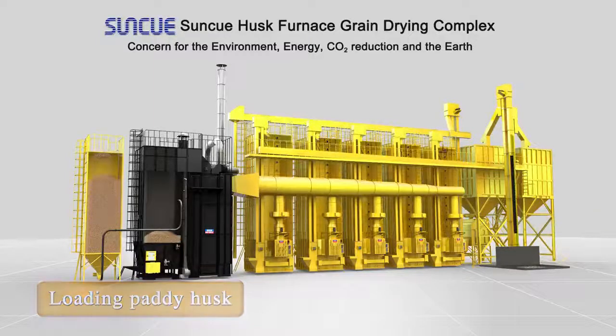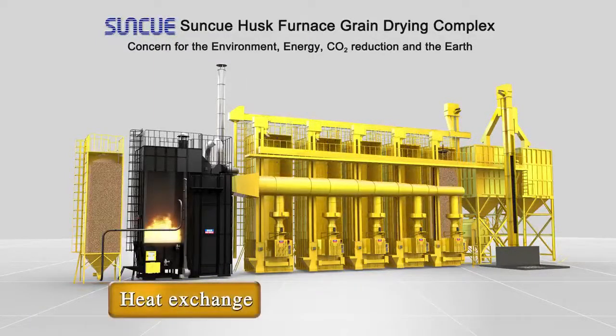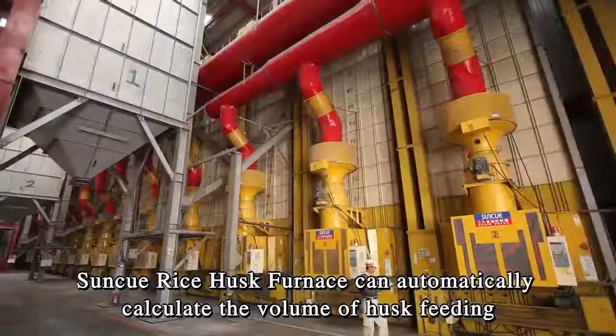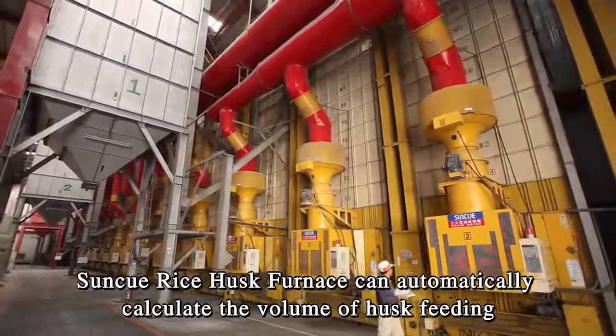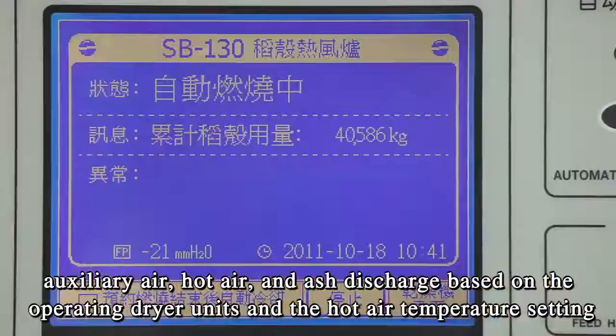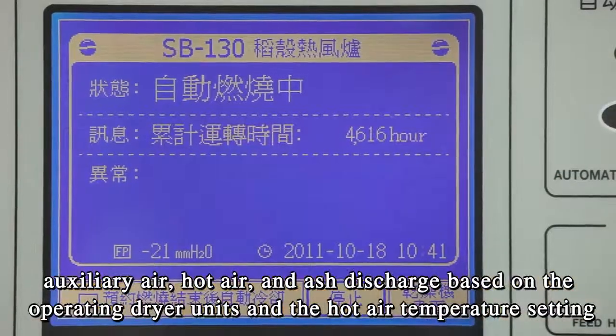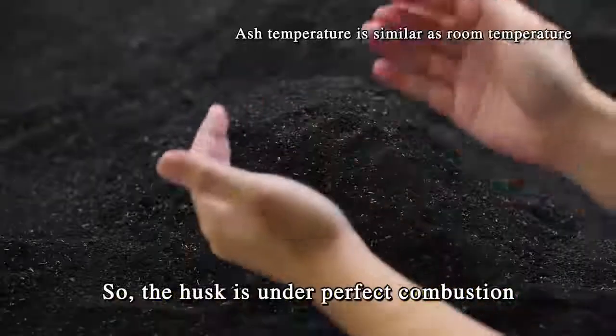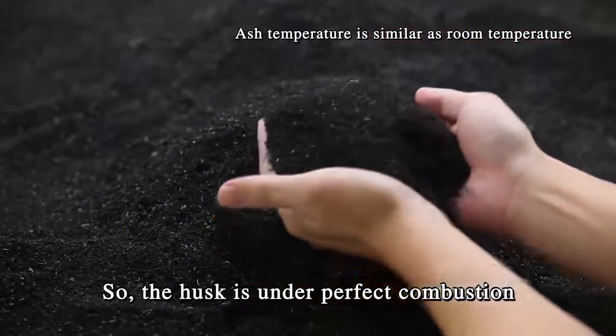The furnace's computer will auto-calculate the required husk feeding volume and blow into the furnace. The hot air will pass through heat exchangers and only clean air will be sent to dryers. Suncue Rice Husk Furnace can automatically calculate the volume of husk feeding, auxiliary air, hot air, and ash discharge based on the operating dryer units and the hot air temperature setting, so the husk is under perfect combustion.